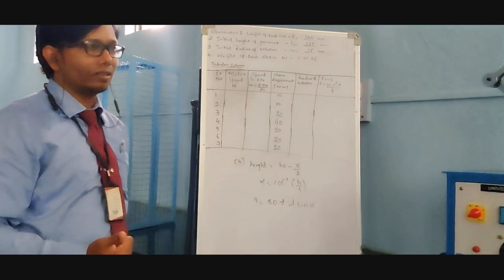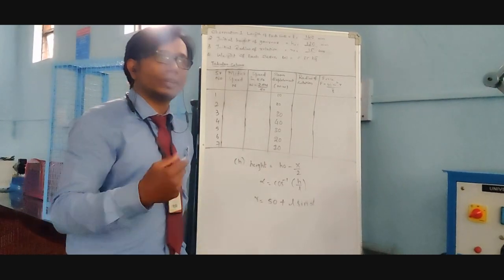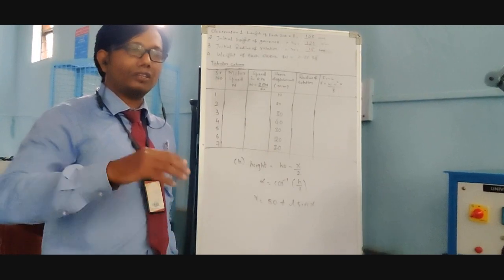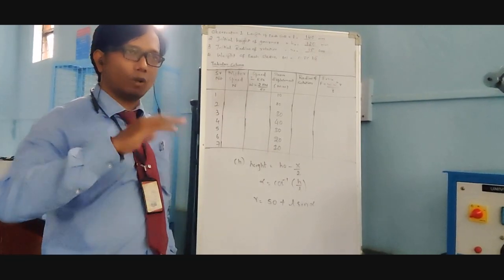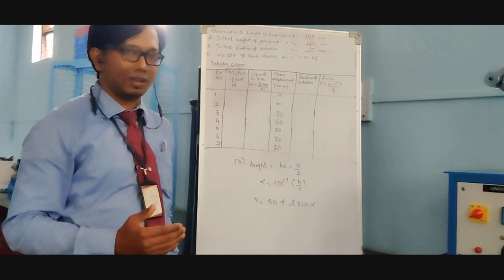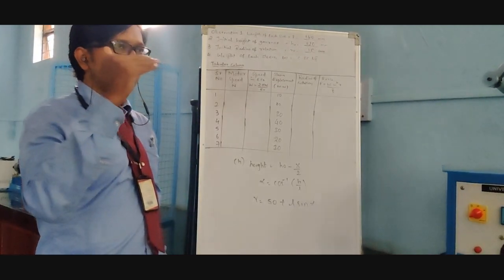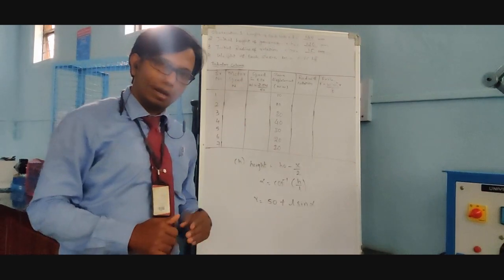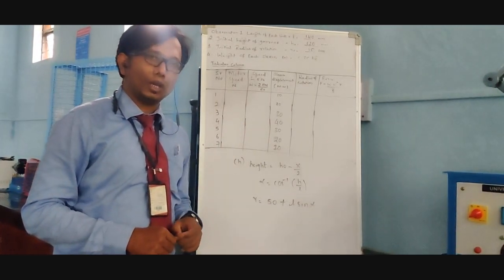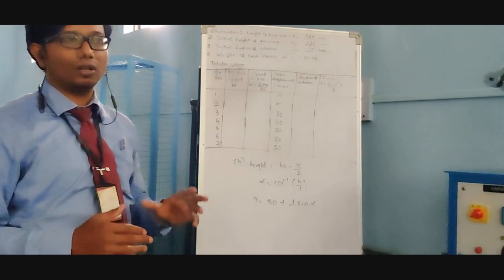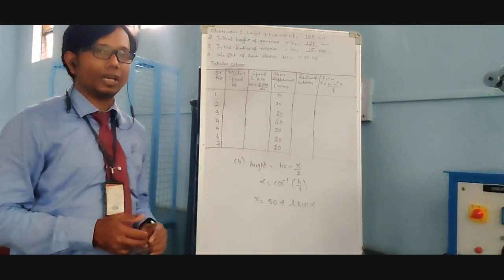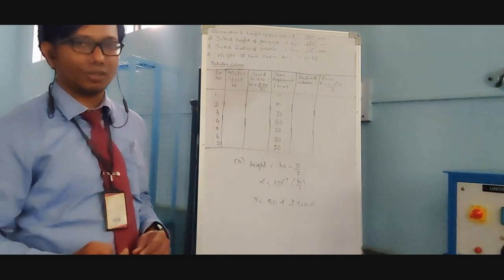Why we are doing this is to see the controlling force with the radius of rotation while rising, which means if I am increasing the sleeve displacement, or the RPM is increasing, and while decreasing, whether we will have the same RPM or not. Why? Because there is always a loss, an error we call hysteresis. We will be checking whether this hysteresis is coming or not.